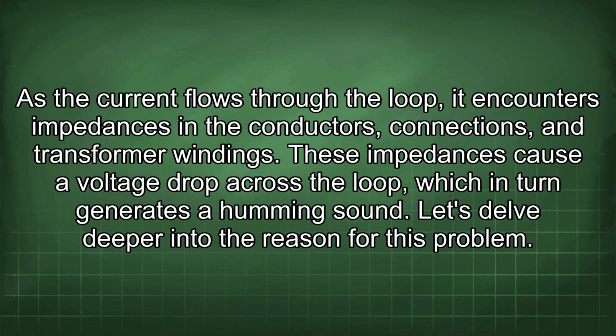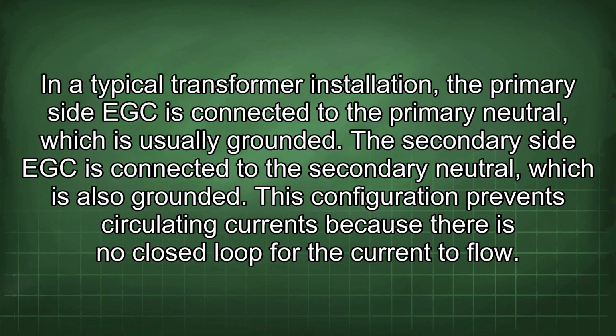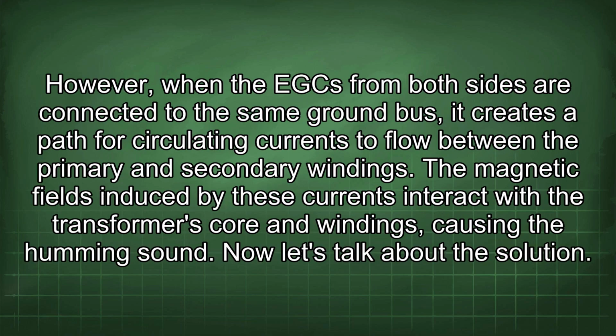Let's delve deeper into the reason for this problem. In a typical transformer installation, the primary side EGC is connected to the primary neutral, which is usually grounded. The secondary side EGC is connected to the secondary neutral, which is also grounded. This configuration prevents circulating currents because there is no closed loop for the current to flow. However, when the EGCs from both sides are connected to the same ground bus, it creates a path for circulating currents to flow between the primary and secondary windings. The magnetic fields induced by these currents interact with the transformer's core and windings, causing the humming sound.